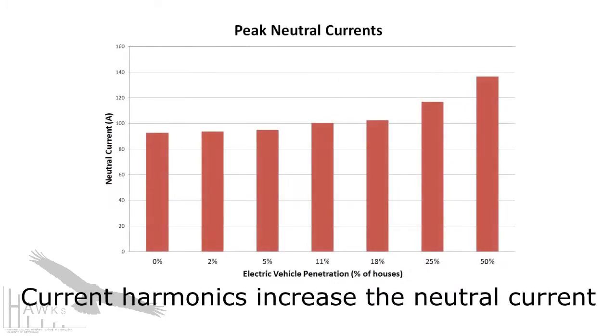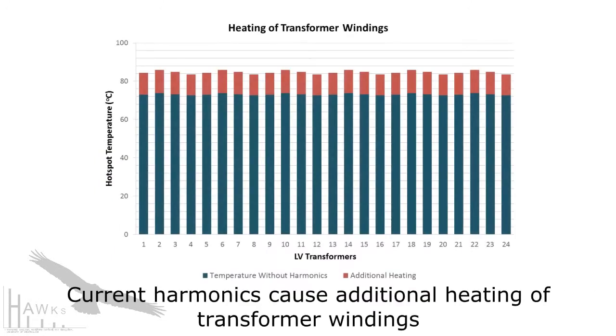After analysing the results of our simulations, we found that current harmonics had made a significant impact on areas of the network. Currents through the neutral cable were increased dramatically due to the presence of triplen harmonics, and significant temperature rise could be seen in the transformer windings.